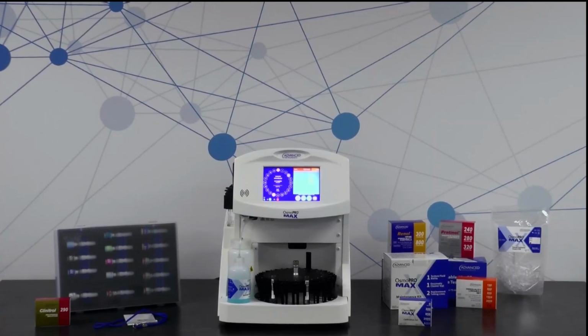Does it have a printer? No built-in printer on this instrument, but it is compatible with a printer that we sell separately. Okay, is QC required after 500 tests? Yes. So QC we require every single day, at least the Clinitrol 290 is required every single day on this instrument. But yes, you'd have to run it after 500 tests as well.